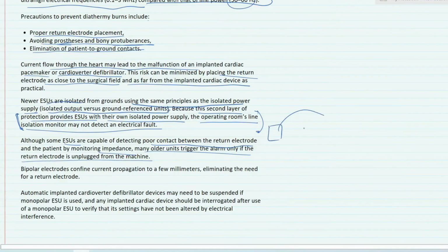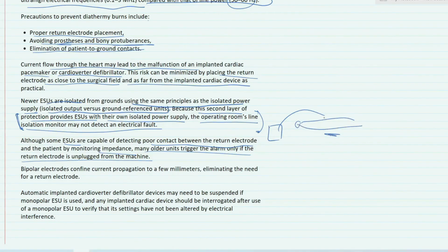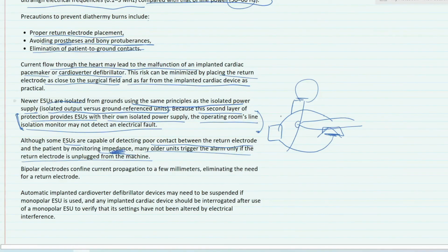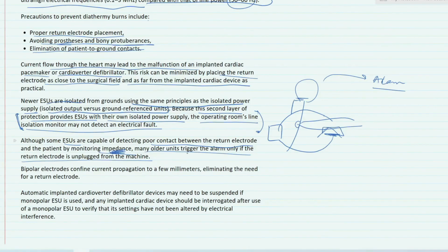Let's say, for example, this is an ESU and we have this tip, and we have this patient lying down here, and it is touching it, and the plate is also touching the patient, and we have that going back. Now if there is a poor contact of the plate somewhere, the modern machine, through a meter, would detect a higher impedance here, and then it would figure out that the contact is poor and give off an alarm, right? But in the older units, they triggered the alarm only if the return electrode is unplugged from the machine, when the circuit is not being completed. So in older machines, the alarm was given when the circuit is not complete, right?